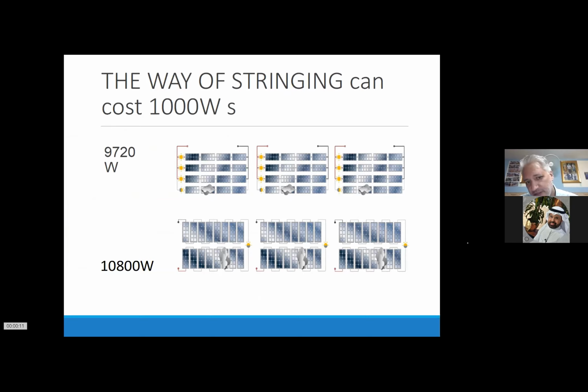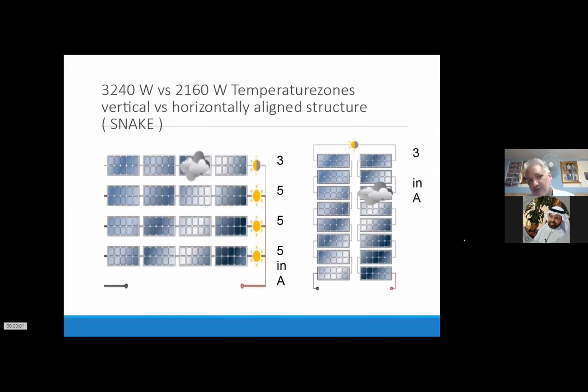So to do a fine tuning and to find strings which are not performing well, or change maybe even the string layout, it's worth it. We're talking about 1 kilowatt for free. So that's almost 1,000 watt missing during a long time. If it's cloud-based, or of course if it's based on some roof, or this is small tiny little shades.